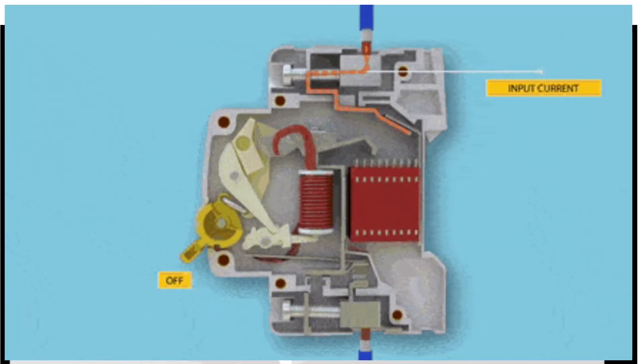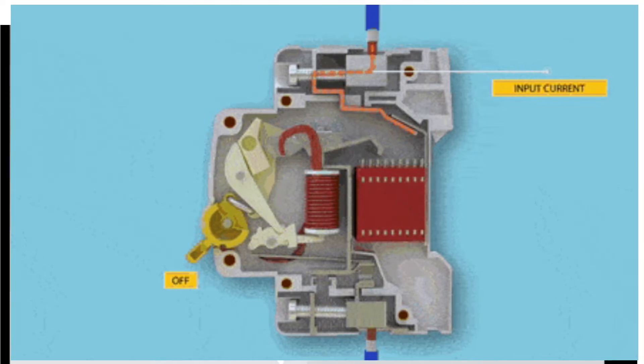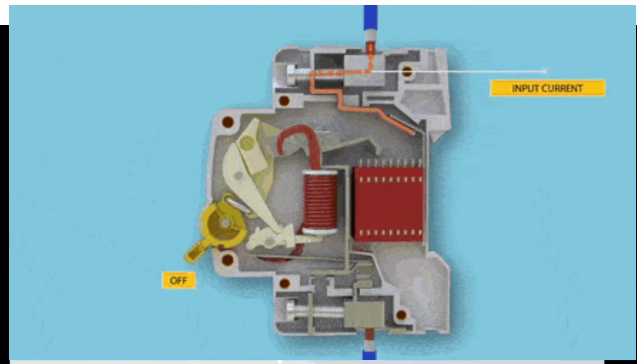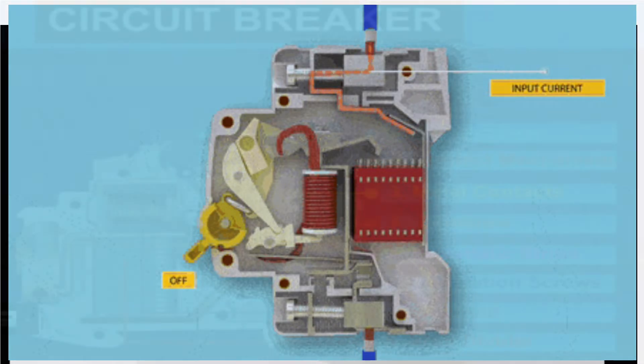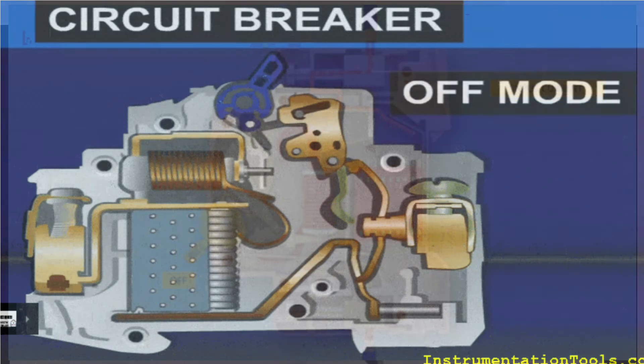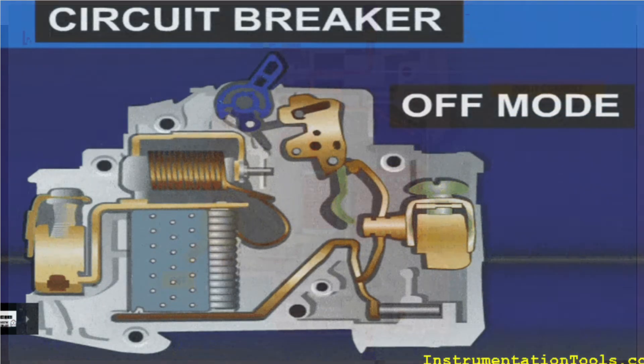Handling MCB is quite safe and it quickly restores the supply. When it comes to house applications, MCB is the most preferred choice for overload and short circuit protection. MCB can be reset very fast and has no maintenance cost. MCB works on the bimetal strip principle, which provides protection against overload current, and a solenoid for short circuit current.